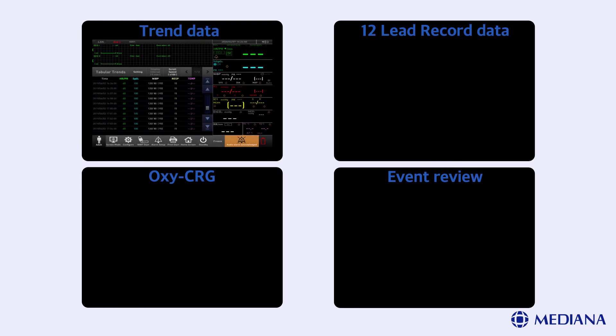Data recording is divided into four types: trend data, 12 lead recording data, OxyCRG and event review. For trend data, the monitor presents trend information in tabular format for all monitored parameters. The newest data appears at the bottom of tabular trends. For the NIBP trends, the data may display the latest measurement.